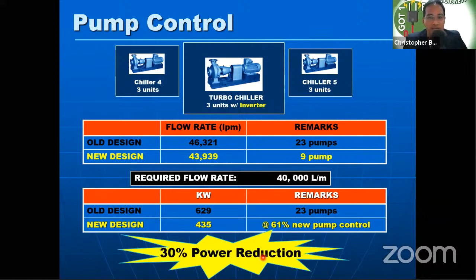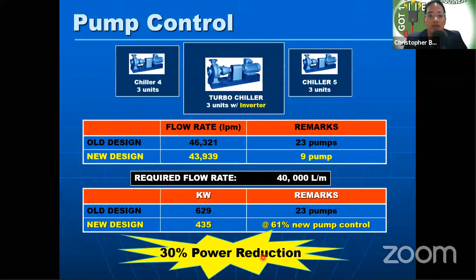In terms of kilowatts, old design was 629 with 23 pumps. New design is only 435 kilowatts, at 61% of new pump control output needed for the new pumps with VFD installed. This resulted in a 30% power reduction. So earlier we had 35% from the chiller, plus another 30% power reduction. That's a huge benefit and very significant for our operation.